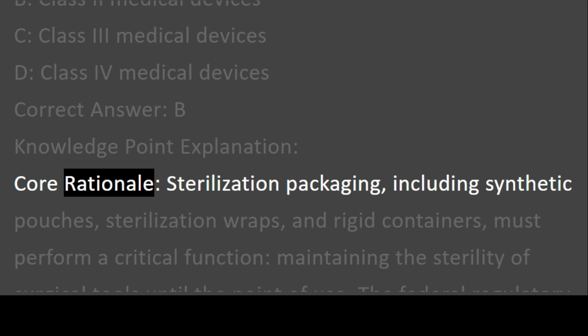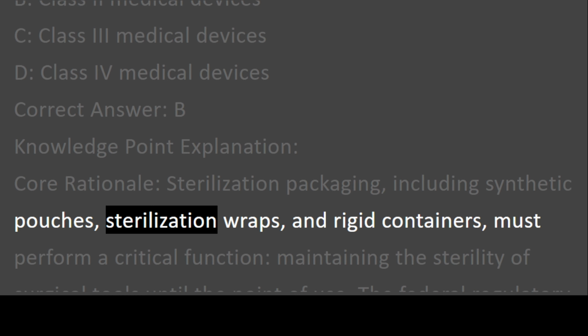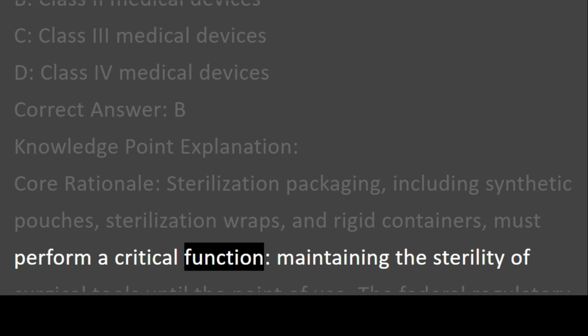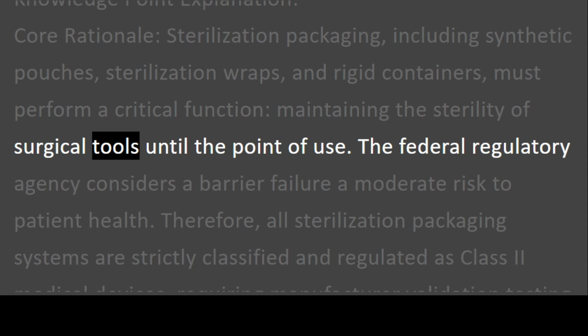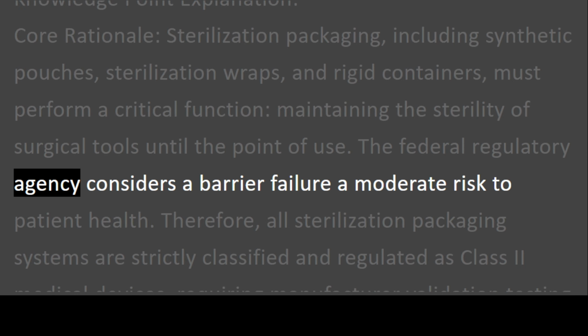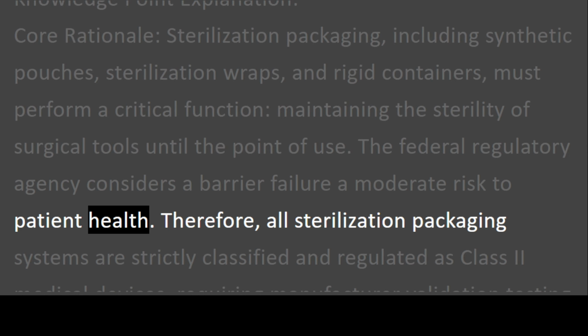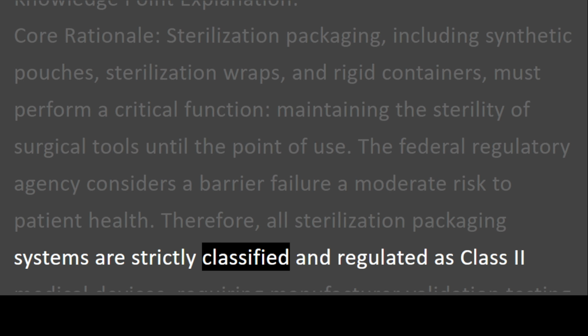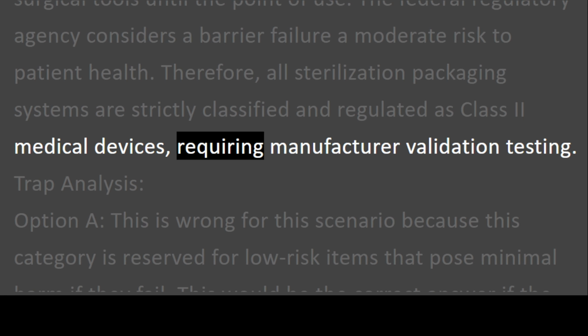Core rationale: sterilization packaging, including synthetic pouches, sterilization wraps, and rigid containers, must perform a critical function, maintaining the sterility of surgical tools until the point of use. The Federal Regulatory Agency considers a barrier failure a moderate risk to patient health. Therefore, all sterilization packaging systems are strictly classified and regulated as Class 2 medical devices, requiring manufacturer validation testing.